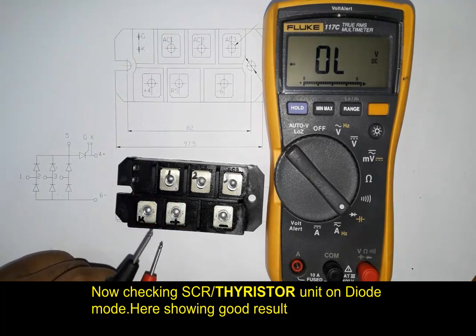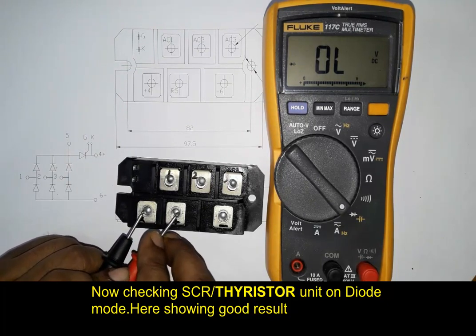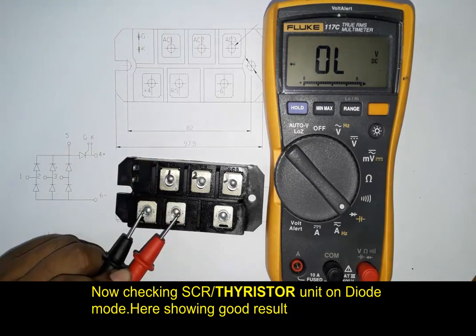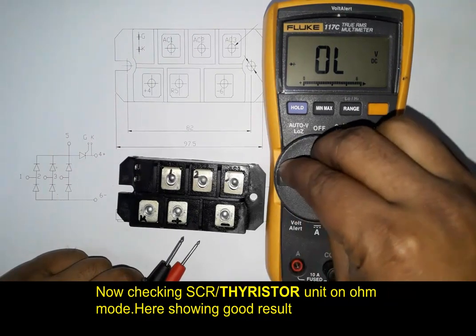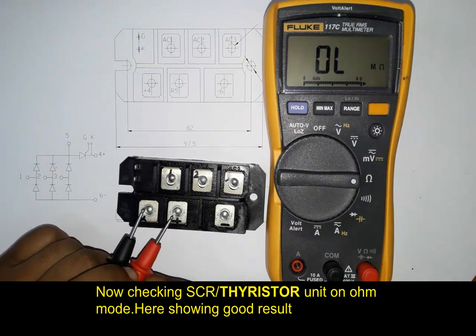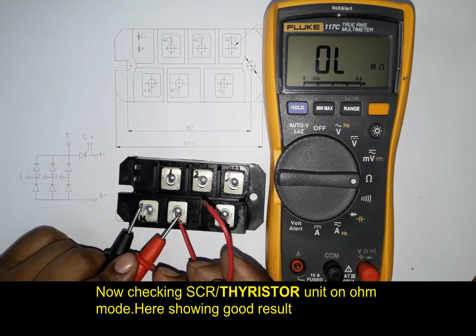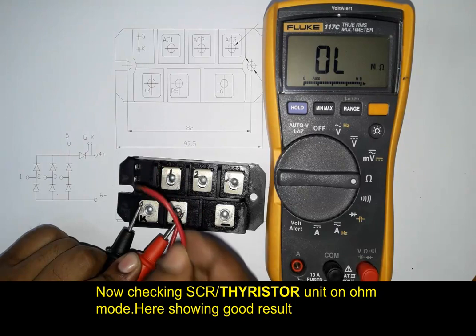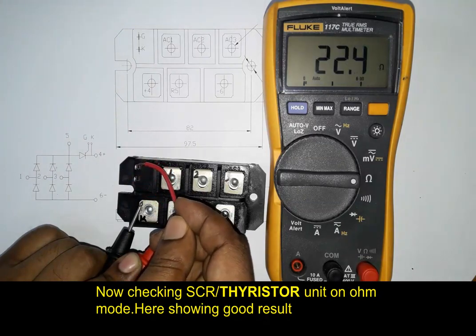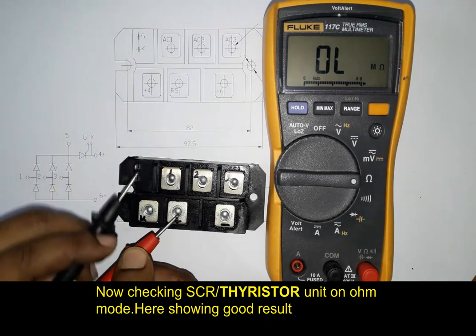We can also test in resistance mode for switching a thyristor. We checked in diode mode but it was not working, so we check in resistance mode right now. Red probe in anode and black probe in cathode, then touching red probe from anode to gate — here showing about 22.4 ohms. That means the thyristor unit is okay and good for working.